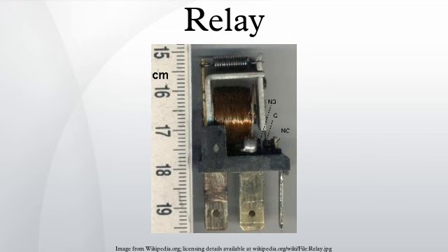The heat energy contained in the resulting electrical arc is very high, causing the metal on the contact surfaces to melt, cool and migrate with the current. The extremely high temperature of the arc cracks the surrounding gas molecules, creating ozone, carbon monoxide, and other compounds. The arc energy slowly destroys the contact metal, causing some material to escape into the air as fine particulate matter. This very activity causes the material in the contacts to degrade quickly, resulting in device failure.